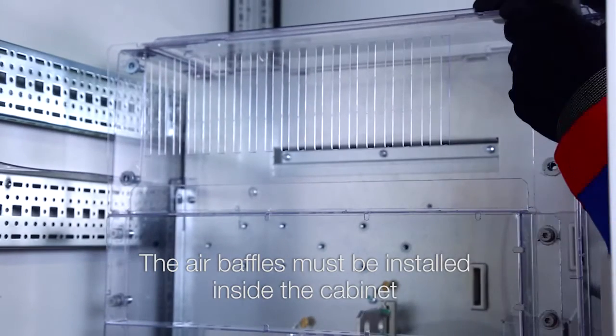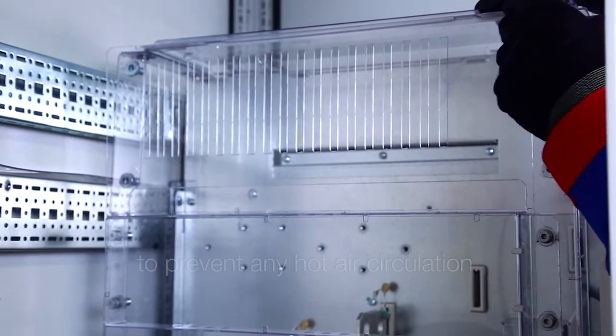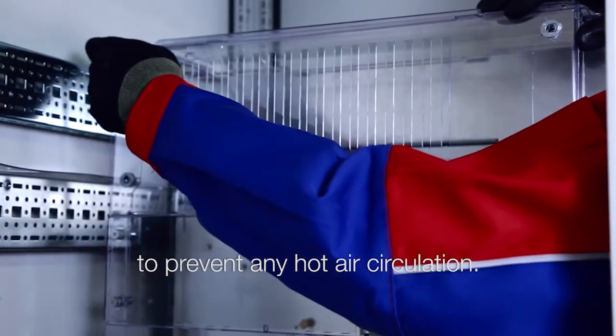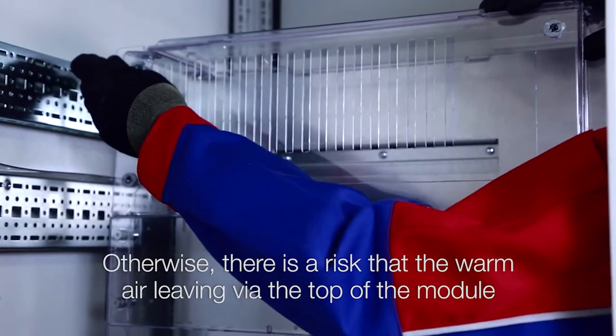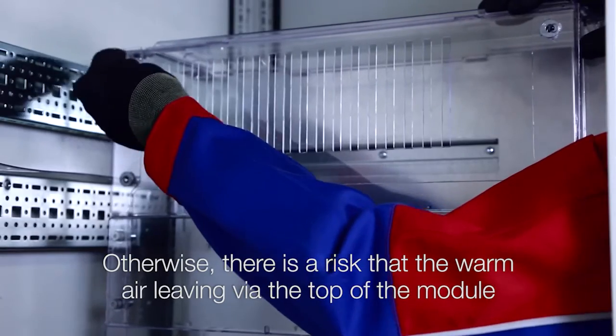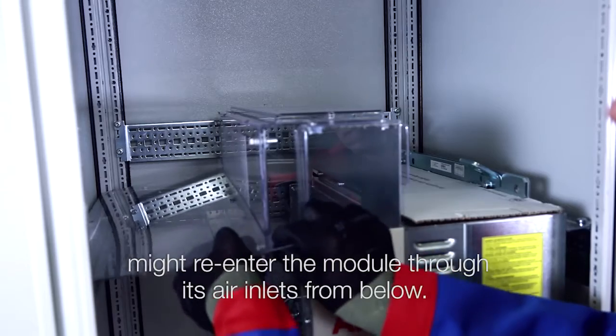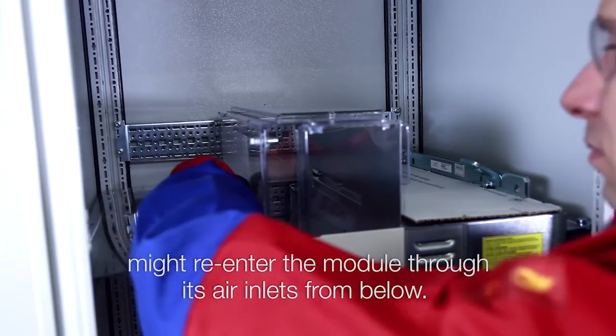The air baffles must be installed inside the cabinet to prevent any hot air circulation. Otherwise, there is a risk that the warm air leaving via the top of the module might re-enter the module through its air inlets from below.